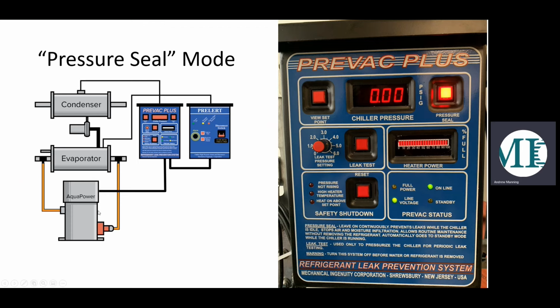It is a 3-phase system, so when we get within 2/10 of the set point, we drop out one of the phases, and then we're on triac control. So that's going to reduce the wattage to maintain that set point there. So it's going to use very little power once it is out of the deep vacuum to maintain and keep the system out of the vacuum for the number of months that you are going to be offline.